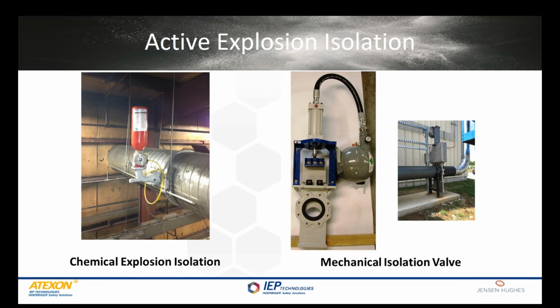The high-speed isolation valve that's shown on the left or the right two pictures, those are basically knife gate valves, orifice knife gate valves that are signaled to activate very quickly and to close within milliseconds to stop that flame from traveling through the duct.